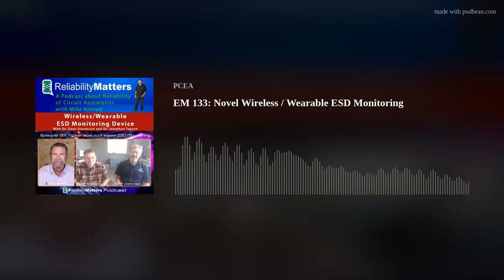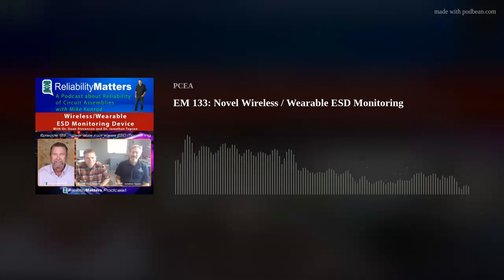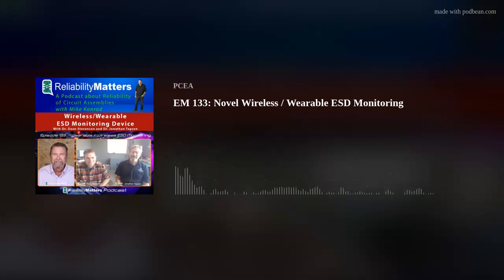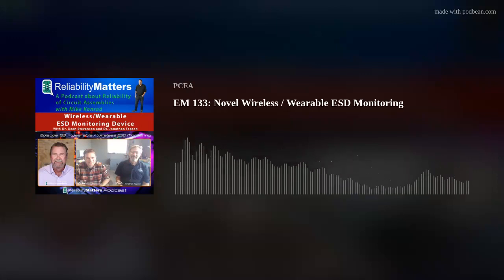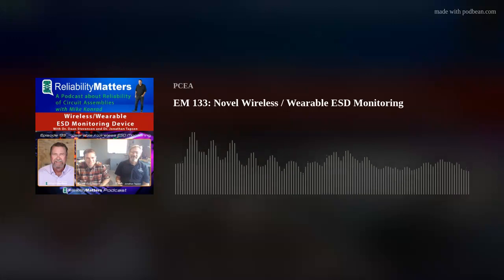Okay, I'll keep the video going. Right now we're showing someone wearing it. They're now turning it on. Yeah, so it turns on and off with a single button that can also mute it. And as you see now, Daan is walking around. And if you can pause there. So what happened there was he walked around on a non-ESD floor, and he generated some charge, got himself down to minus 400 volts or so. And then he touched a grounded point.